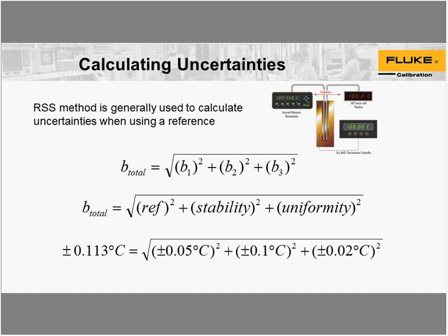Now, if you're calibrating directly to the display of the unit itself, in this particular example, you would negate that reference that we're showing as an external and then simply build in your display accuracy. So again, that gives you an example of how to put together a quick uncertainty analysis for a well with a reference.